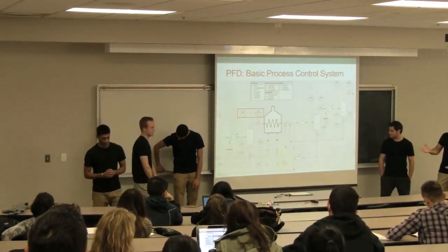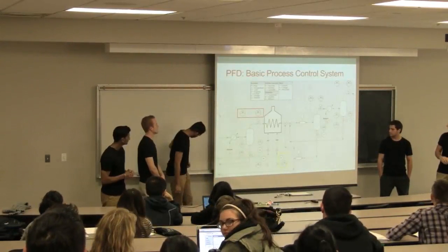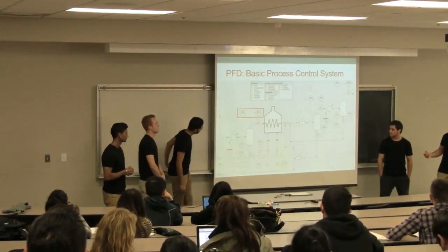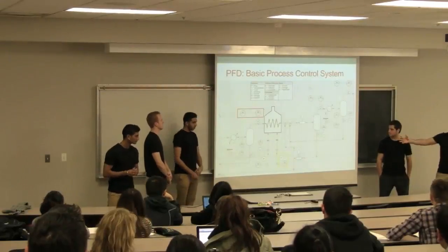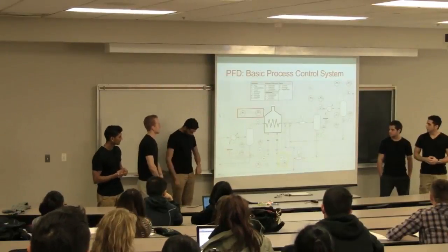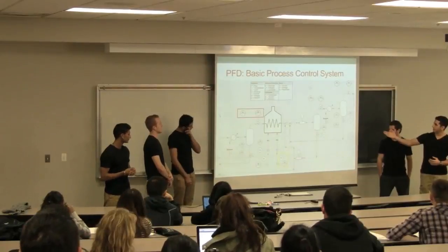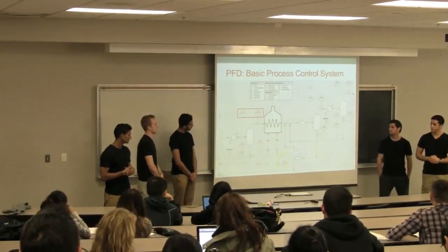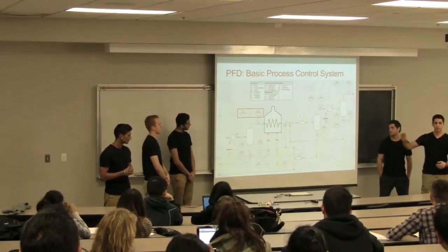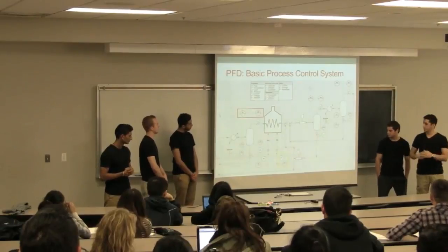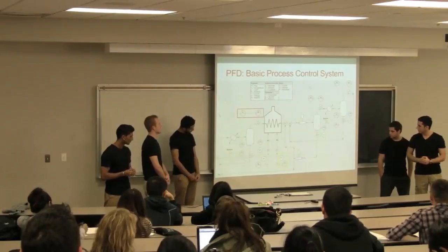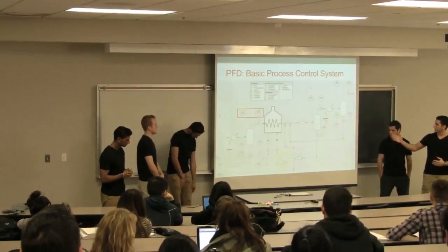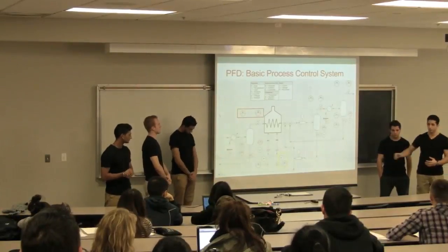Okay. So here's the P&ID after our modifications. Some of the highlights that show you here, like the red box over there, shows a pressure control that regulates the pressure inside the flash tank, the first flash tank, by adjusting the vapor flow out. We're going to be doing a further HAZOP on that node in the upcoming slides. We also have a flow controller, the yellow box over here, which regulates the natural gas inflow into the furnace by adjusting the valve opening.